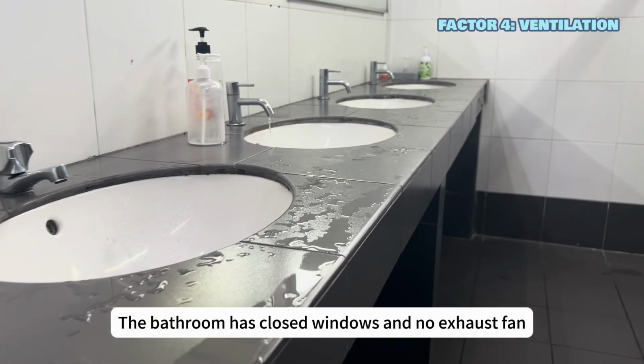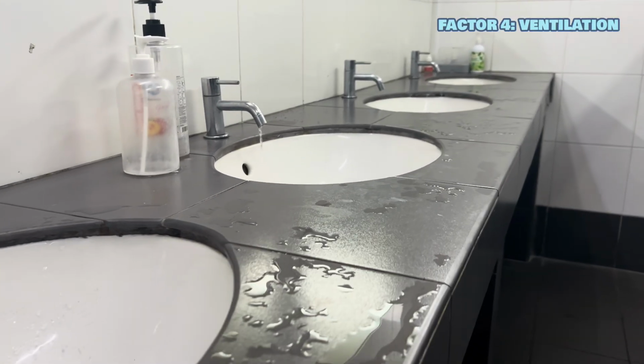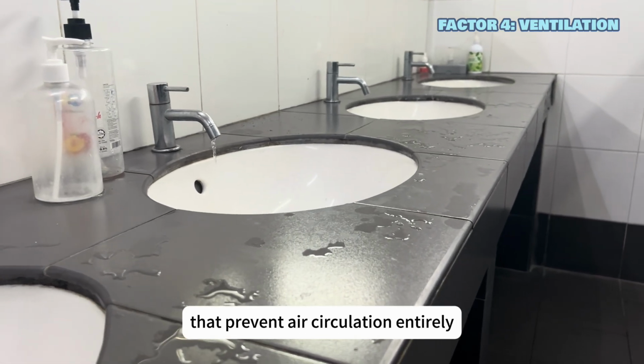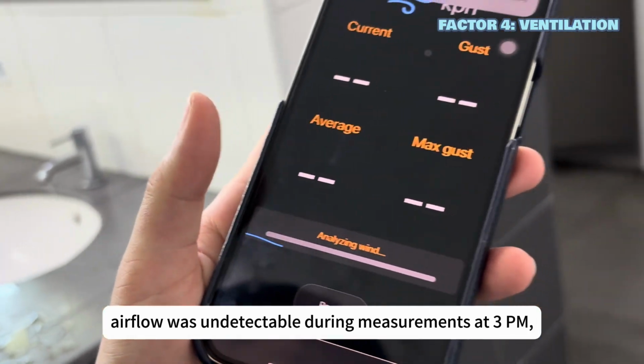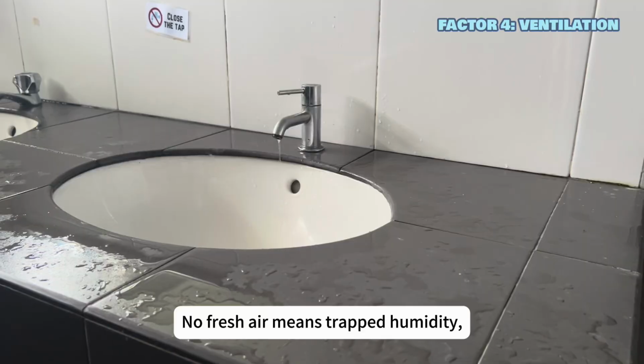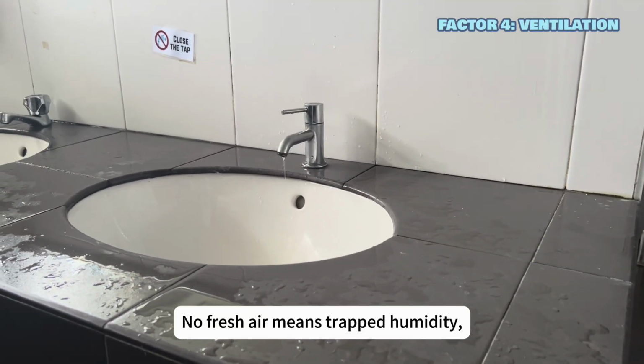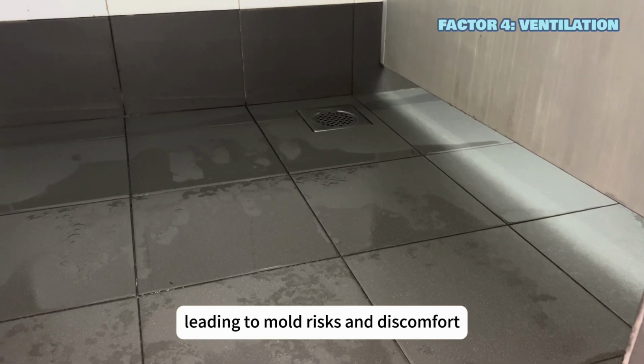The bathroom has a closed window and no exhaust fan, which prevents air circulation entirely. Airflow was undetectable during measurements at 3 p.m. No fresh air means trapped humidity, leading to mold risks and discomfort.